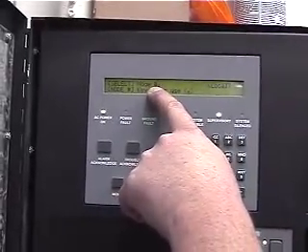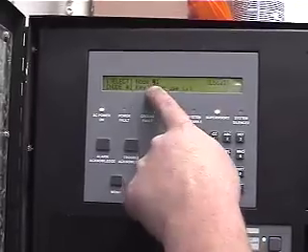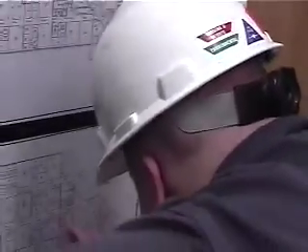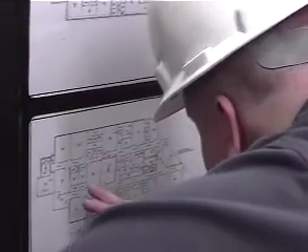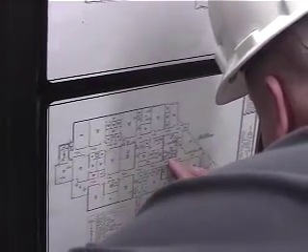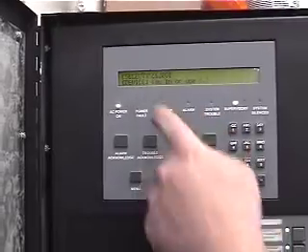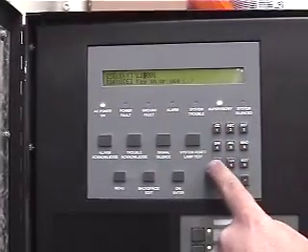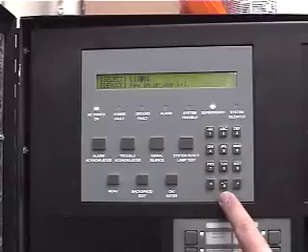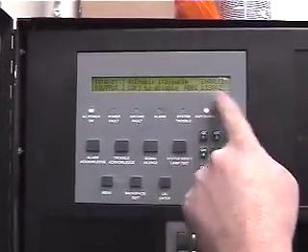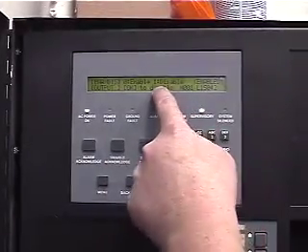So here's where you have to know the node. So you go node 1, like if we want to bypass the smoke here, that one is, let's see, where are we at? Node 1, loop 1, sensor 42. So we got node 1, okay, loop 1. And then S or M, so I go S, and then I can go 042. That gives me my loop, press OK, then I can say 0 for enable, 1 for disable.